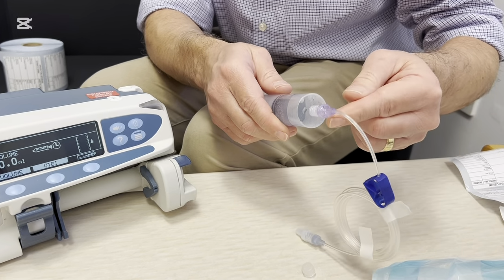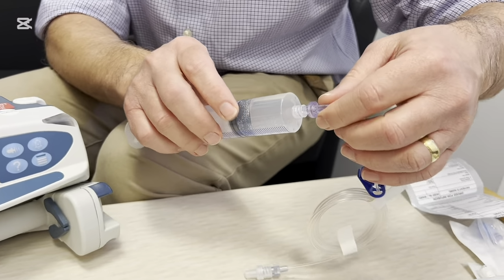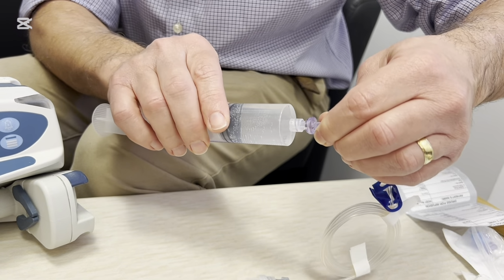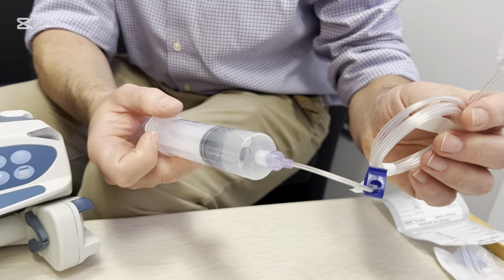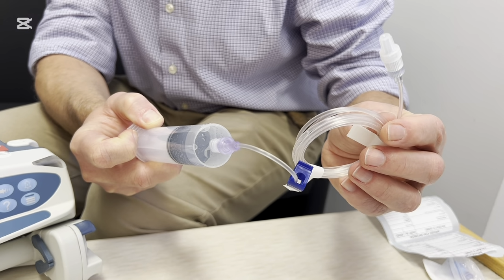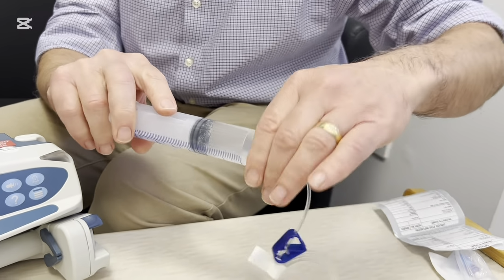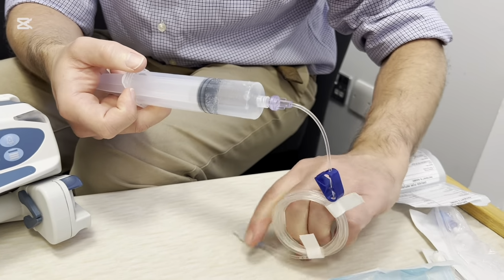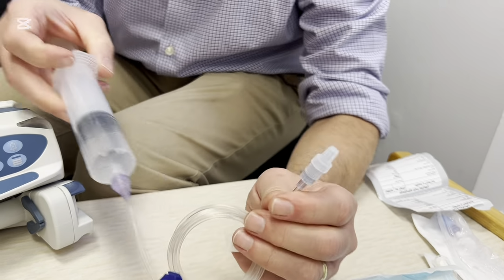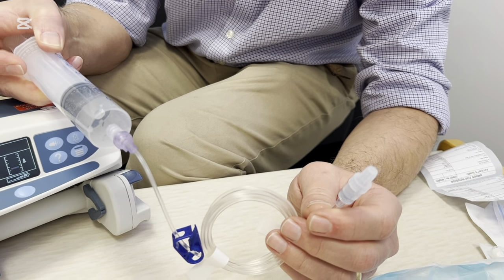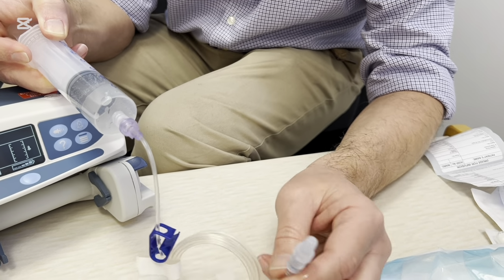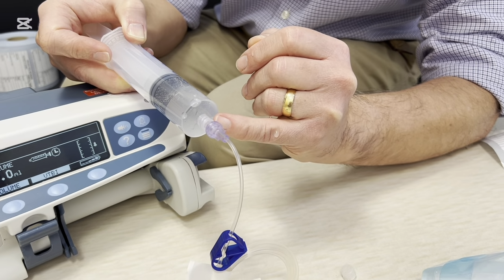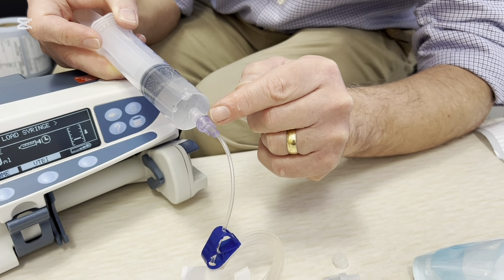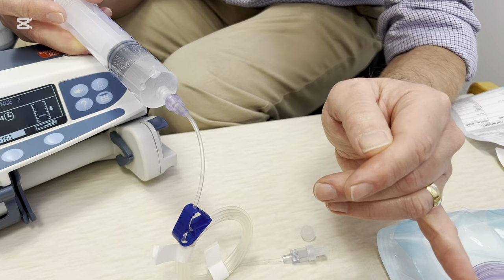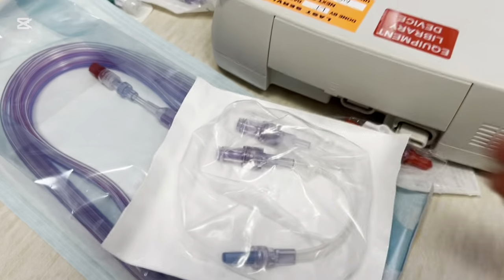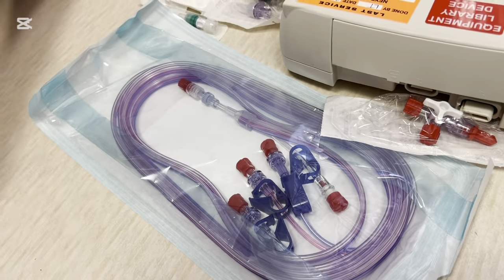What we use here is an anti-siphon valve. So all syringe pumps ideally should have an anti-siphon valve on the line, and you need to prime the line. What we have found with some devices is that if you tighten the anti-siphon excessively, it can actually close the diaphragm and stop any fluid. This one doesn't seem to be doing that, but with some of the total intravenous sets that we've got, we have noticed some problems with some of those devices, and we'll get to that later.